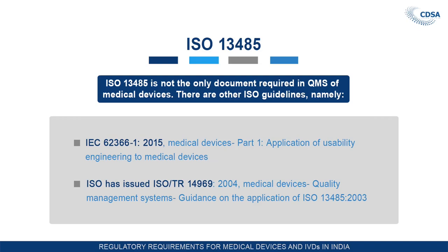ISO has also issued ISO 14969:2004, Medical Devices, Quality Management System Guidance. Now, this ISO is a guidance to the application of 13485. So, if you want to apply 13485 in your plant, you have to go through this ISO to understand how to apply it.